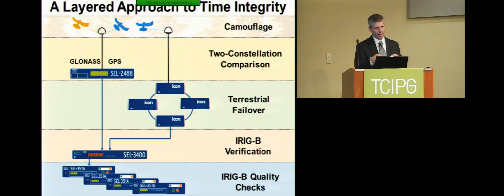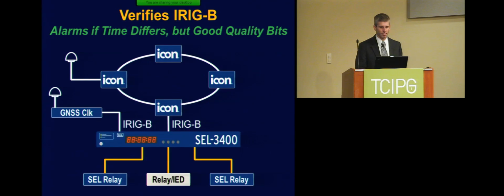Finally, all the way down at the IEDs, they do a great job of checking the frame structure and robustness of the incoming IRIG signal. If they find a problem with it, they can throw a flag and disregard all protection or other elements that rely on absolute time.